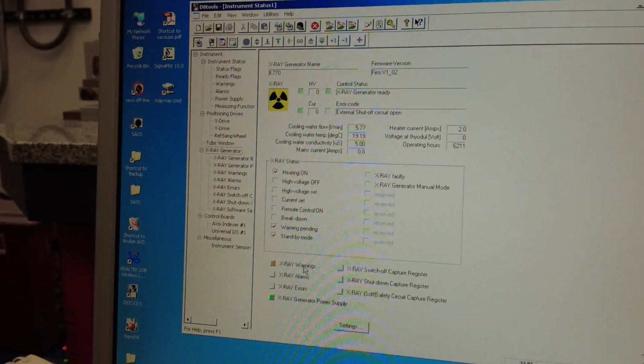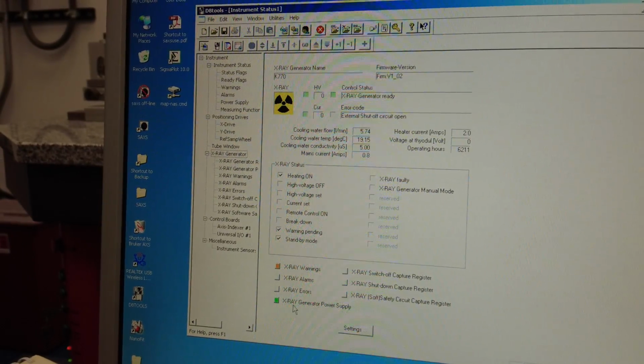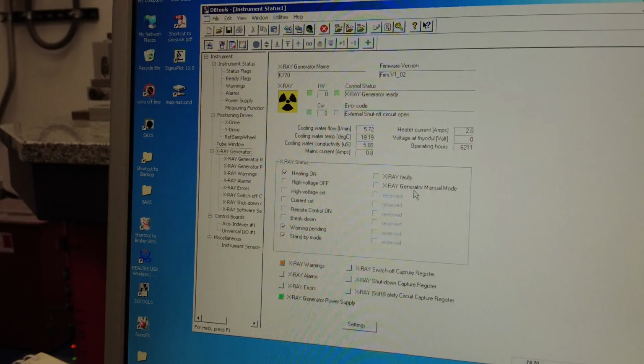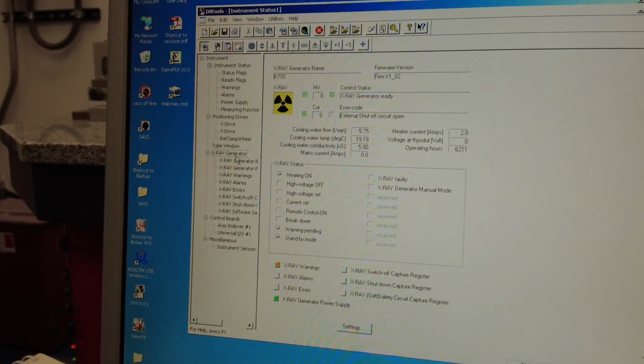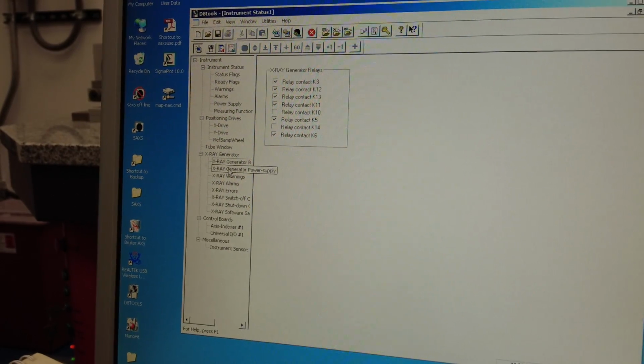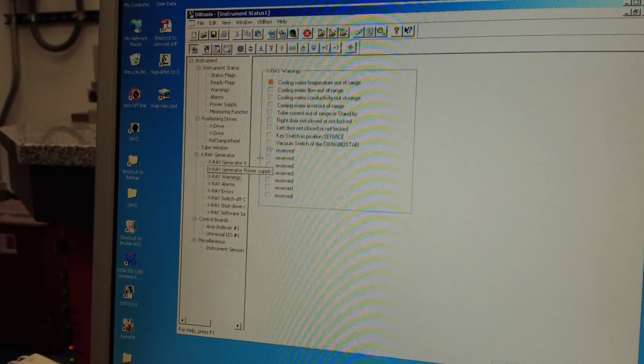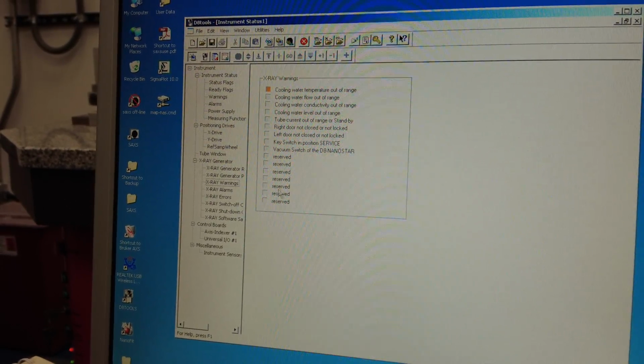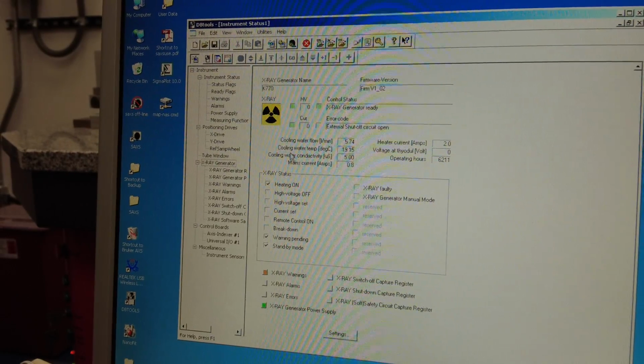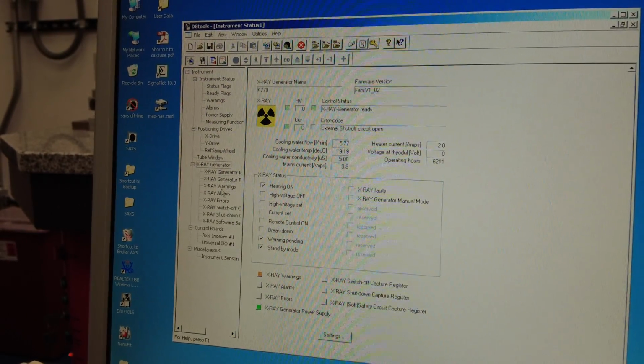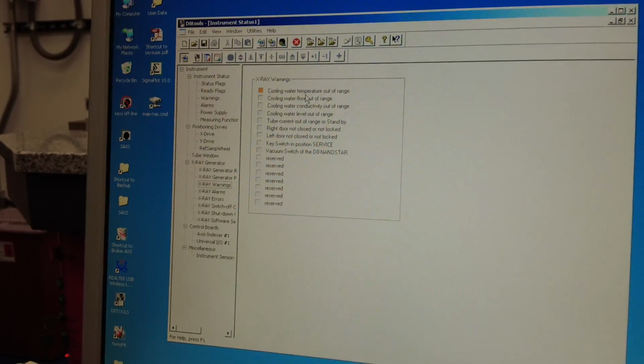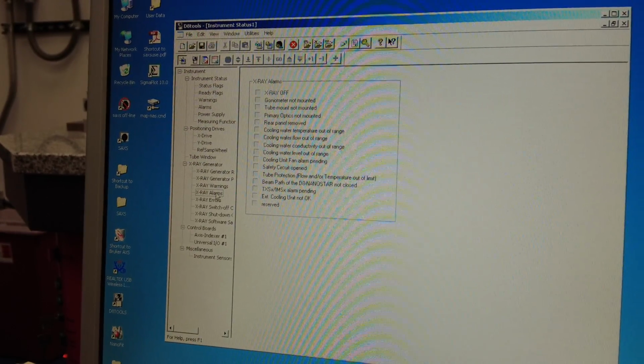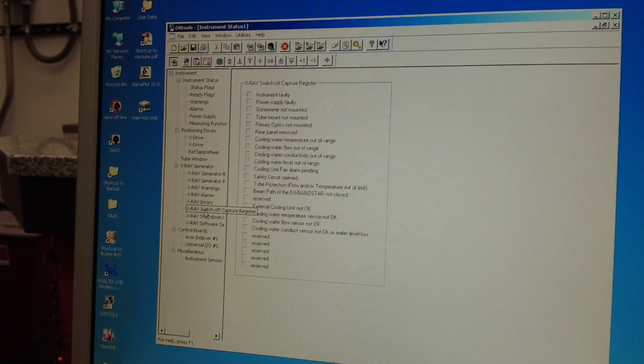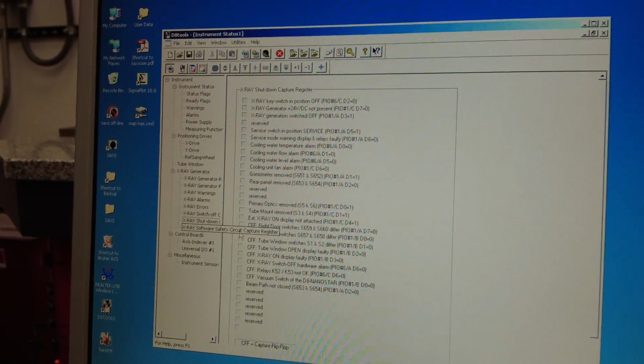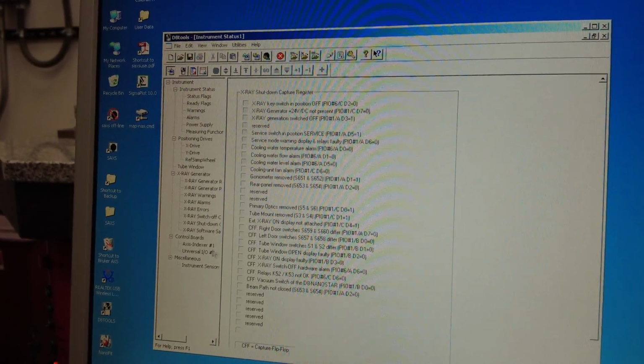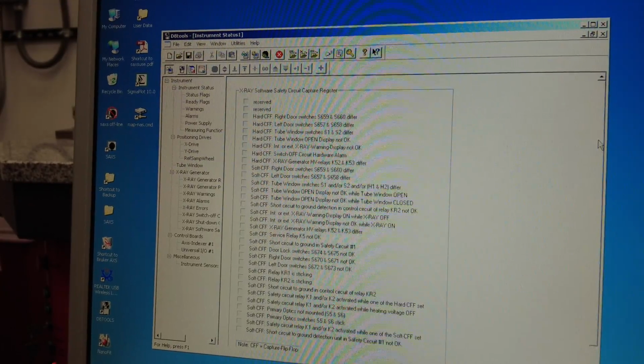It just shows me an X-ray warning. It just shows that the power supply is okay, it's on. It doesn't show faulty, it doesn't show anything else. So I'm going to go over all these: generator relays, power supply, warnings. It shows the cooling water temperature out of range, but over here the cooling water temperature is 19 degrees. So I'm not sure why we have this warning. Alarms, there is no alarms. Errors, switch capture, shutdown. There is literally no error over here.